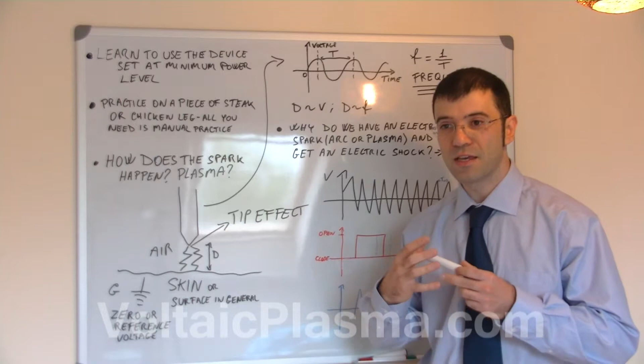But as we've discussed in other videos, that low power level is quite important because it allows you a very high degree of accuracy. Now, let's talk about another important thing, which is the frequency of the device. The output frequency of the device is not the standard 50 Hz that we all know in the mains voltage, but it's much higher than that. The reason for it is that if the frequency was as low as the mains frequency, 50 Hz or 100 Hz, 200 or even 1 kHz, we would actually feel an electromuscular stimulation.